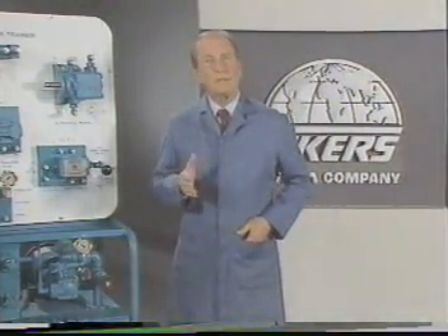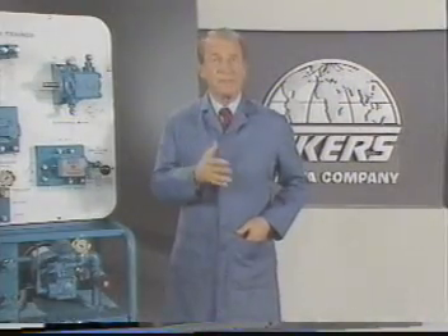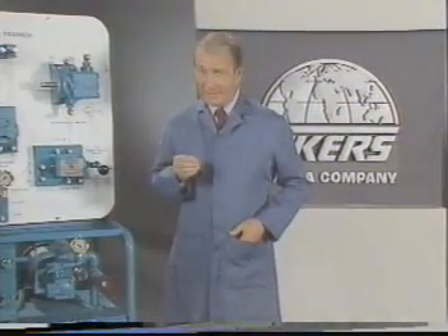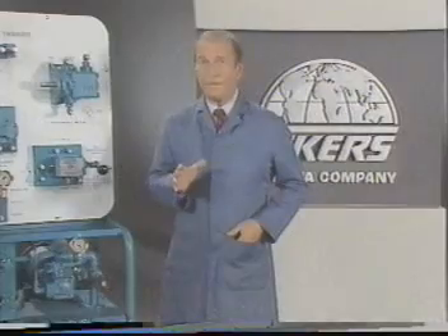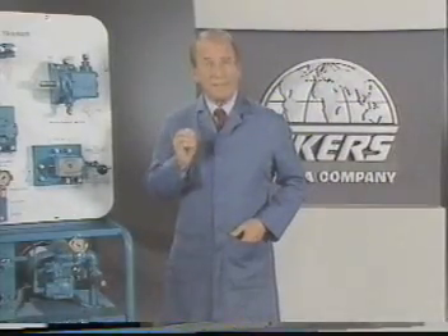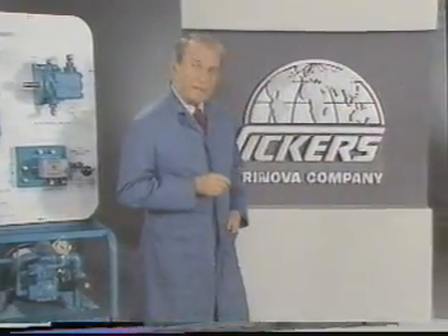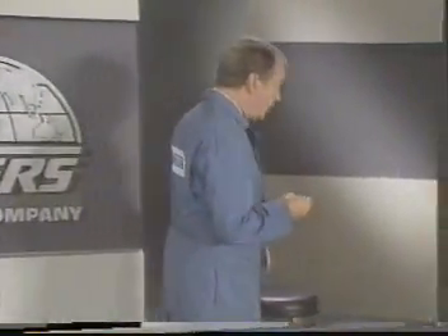Be sure it doesn't go to a cylinder or a motor that's supporting a load. If it does, either lower the load or support it so that it can't fall. An accumulator, too, stores oil under pressure, even with a machine shut down. If you're unsure about it, find someone who knows before touching a thing.